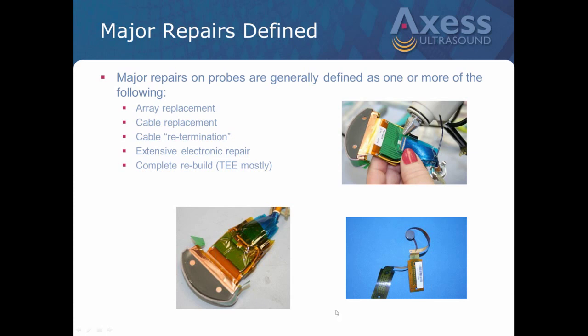Okay, we got a question from Wayne. What does the FDA say about replacing arrays? The FDA, they don't regulate the replacement arrays. However, it is a very good idea. And let me back up. The FDA does say that the replacement array's acoustic power cannot exceed that of the original equipment manufacturer, and it must be within a certain range of what the original equipment manufacturer's array's performance is from an acoustic power standpoint.